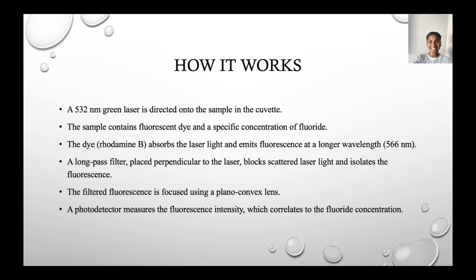Now, this filtered fluorescence we will be able to pick up through our lens, which is then detected through our photodiode, also known as our photodetector, which we have within our device. And this picks up on the fluorescence intensity, which will then display as our specific fluoride concentration.